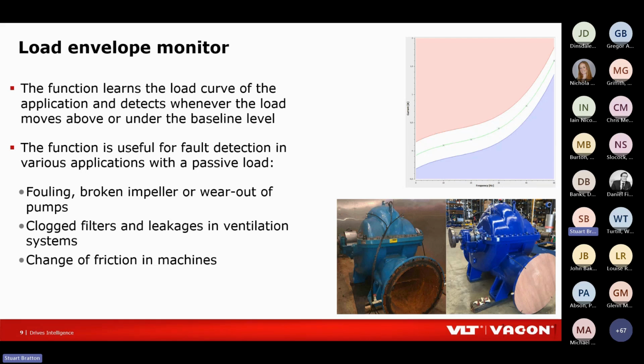The next function is something we call load envelope monitoring. Here the drive, again, makes a baseline, so it learns the expected RMS output current for any given motor speed. In this case, we can program into the drive thresholds above and below that expected current to give us an indication of when we're pulling more current than we might expect, or less current. So this gives us the opportunity to detect things like fouling in pumps, a broken impeller, or maybe a gearbox starting to seize up on a conveyor. Who knows what it is?